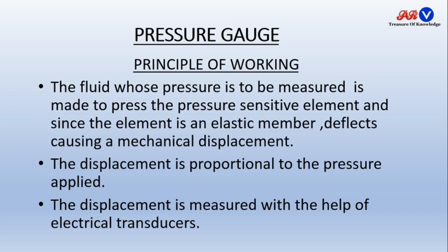So principle of working of pressure gauge: the fluid whose pressure is to be measured is made to press the pressure sensitive element, that is Bourdon tube, and since the element is an elastic member, it deflects, causing a mechanical displacement. So pressure to be measured is applied to the Bourdon tube, which is elastic in nature, and whenever pressure is applied, it will produce some mechanical displacement.